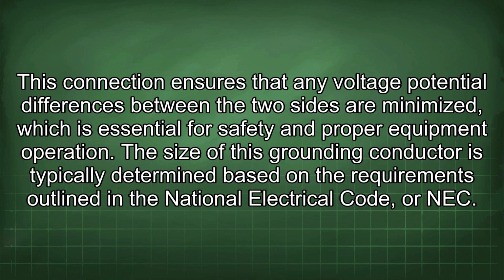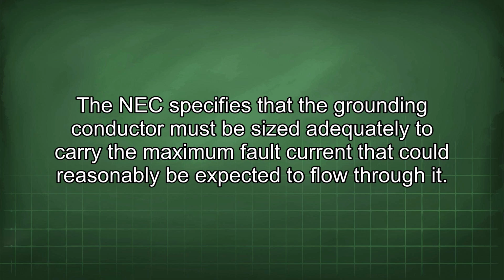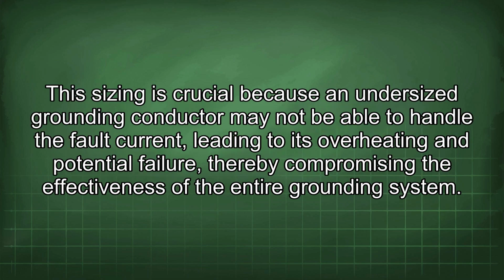The size of this grounding conductor is typically determined based on the requirements outlined in the National Electrical Code, or NEC. The NEC specifies that the grounding conductor must be sized adequately to carry the maximum fault current that could reasonably be expected to flow through it. This sizing is crucial because an undersized grounding conductor may not be able to handle the fault current, leading to its overheating and potential failure, thereby compromising the effectiveness of the entire grounding system.